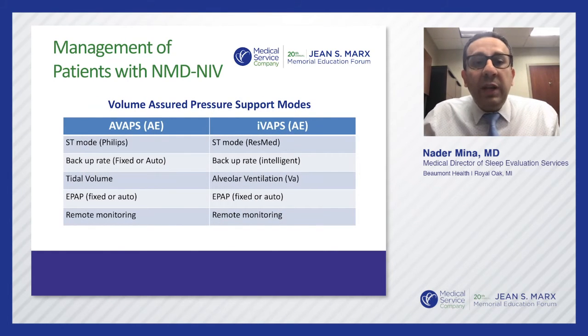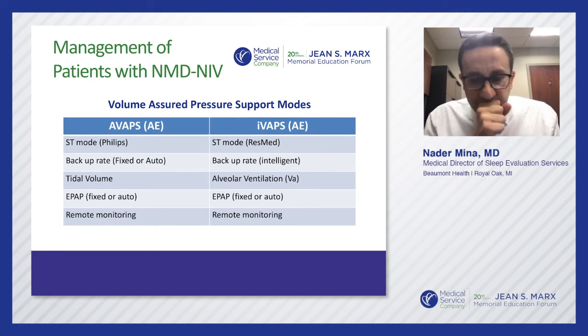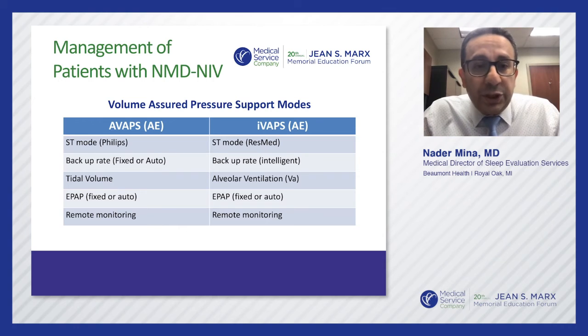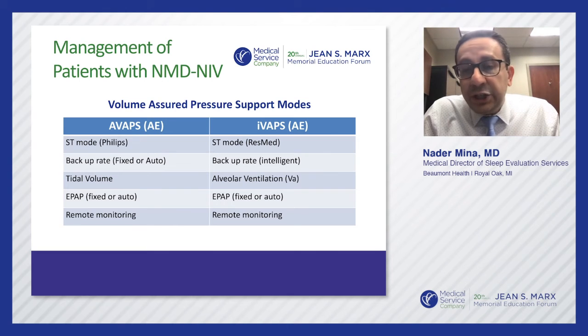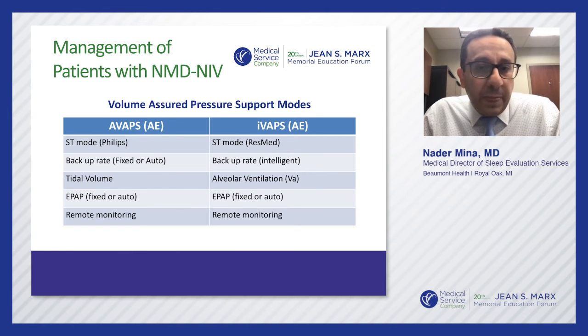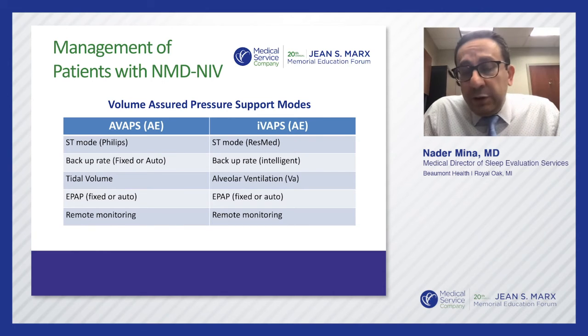Talking a little bit about volume assured pressure support modes. These are two modes that we use usually, which is the AVAPS, which stands for average volume assured pressure support, and IVAPS, which is the intelligent volume assured pressure support. Both of them have the AE feature, which is the auto EPAP feature. Both devices, as you see, one is made by Philips, one is made by ResMed, and both of them function in ST mode, spontaneous timed mode.